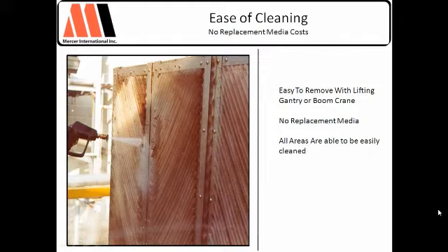that's a problem. So as you're comparing, contrasting, and considering various designs for your next application or for upgrading what you have, I'll tell you, that's a good test. If you were to put sand in there, are the sand particles going to find their way out? If they are, you've got a good design. If they're not, you have a problem. Ease of cleaning. If you're able to clean the pack all the way through, you've got a good design. If you can't, I think you're in a little trouble.